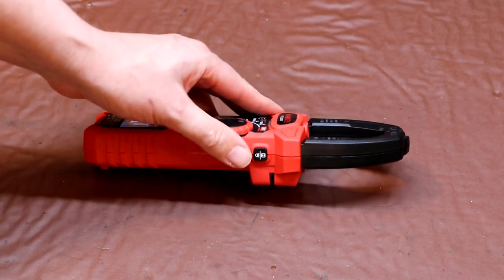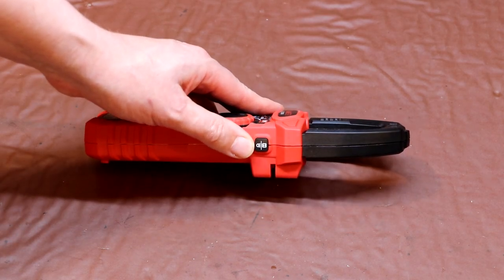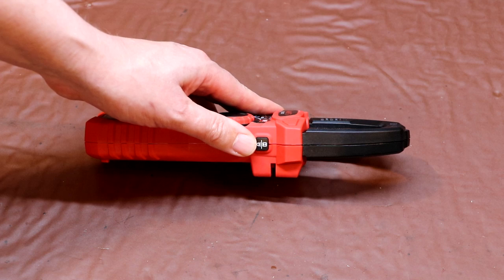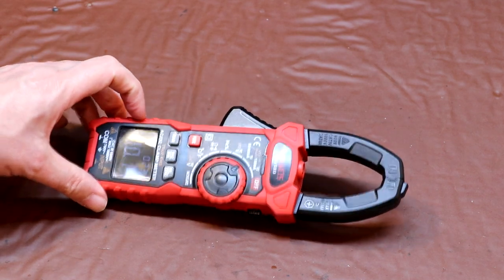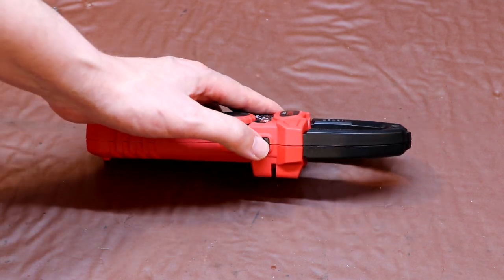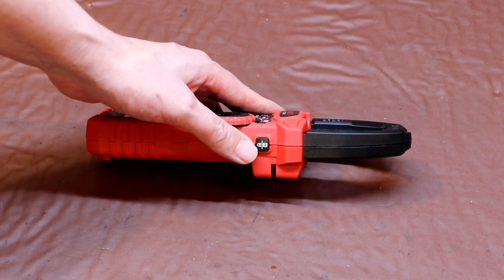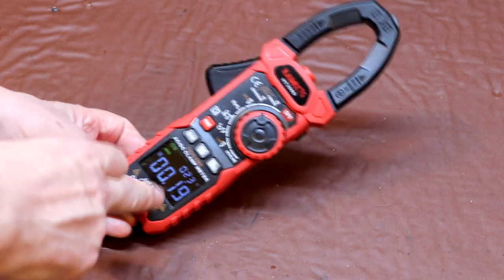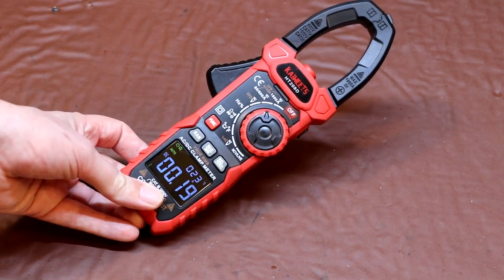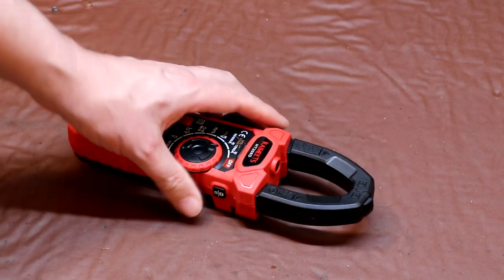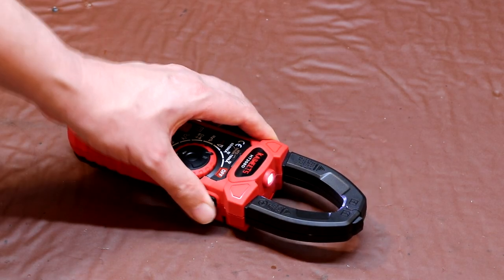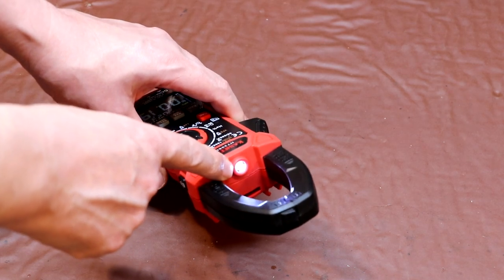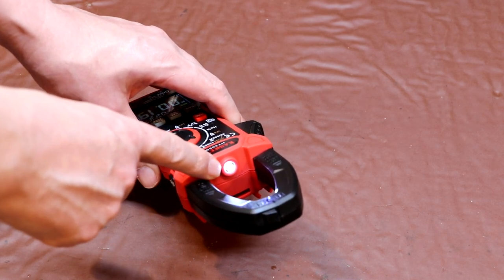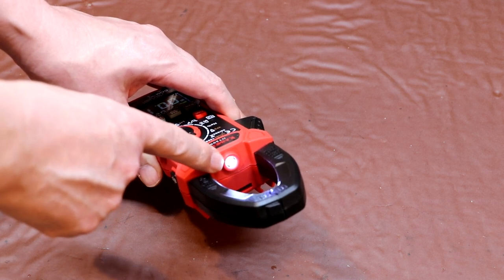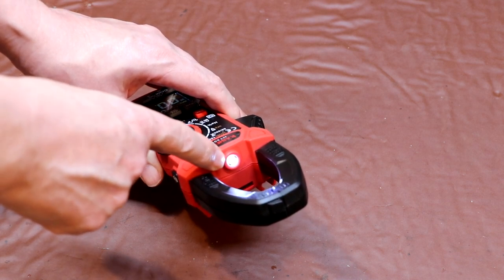So on the side of the instrument here, we've got a dual function push button. If you press the push button once, it works as a hold function. So if you're taking a reading, but maybe you can't see the display on it, you can take your reading, press the hold, and that'll take a snapshot of that reading. So it's now holding that figure on the display here, so you can look at it at your convenience. Now if you hold the button again, or press it again, you can see that an LED lamp comes on the front of the instrument, so that's an LED torch, and of course that's useful for those people that like to carry out high voltage current and voltage measurements in darkness.